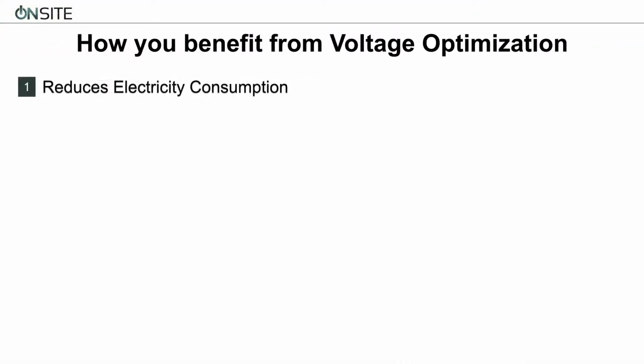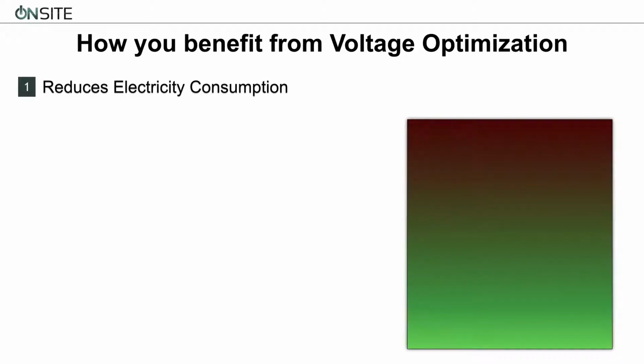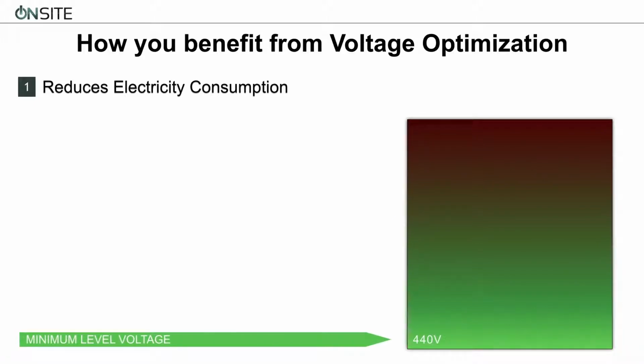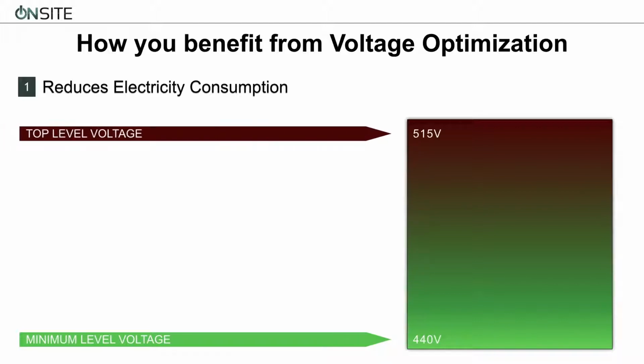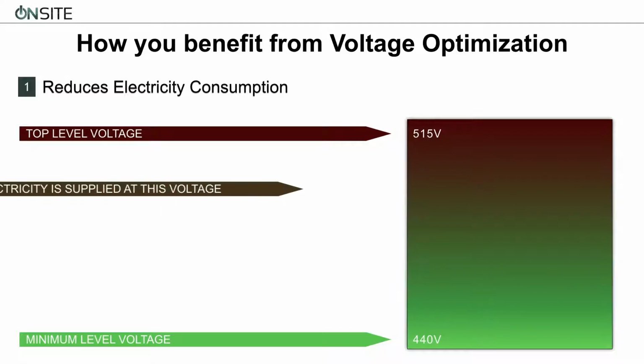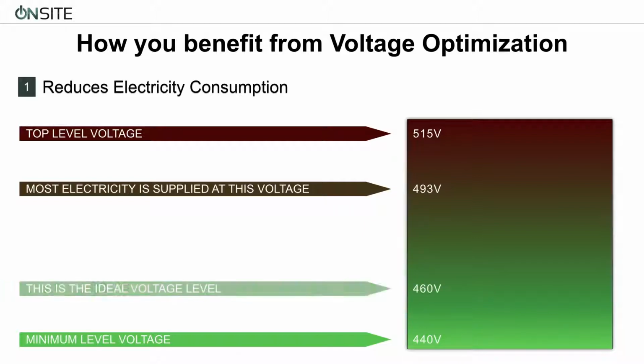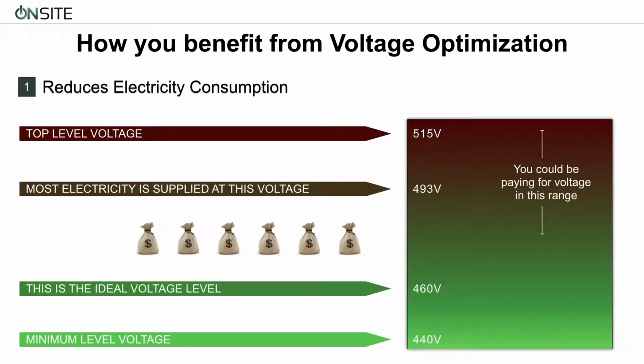Well, first, voltage optimization reduces your electricity consumption by managing the voltage that's coming into your building. The minimum voltage level coming into your building or facility is usually around 440 volts, but it could be as high as 515 volts. But typically, the average voltage is 493 volts. The problem with this is that the ideal voltage level is 460 volts. You might be paying for voltage that's much higher than your building needs, resulting in significantly higher electrical costs.